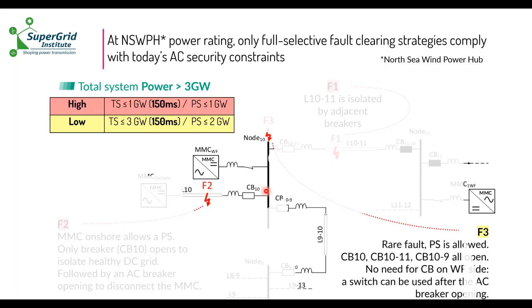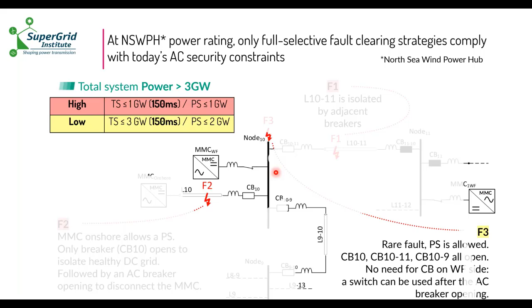You don't need a fast opening. You can open an AC breaker on the other side 100 milliseconds after, and then you can use a switch here. So that's the kind of reasoning we use, taking into account all these constraints to choose what technology is feasible and more economical for a given situation in the network, to optimize the network in the end.